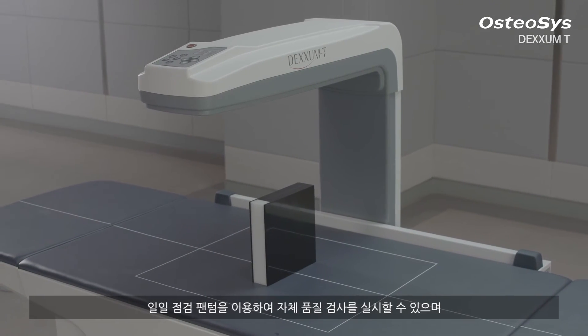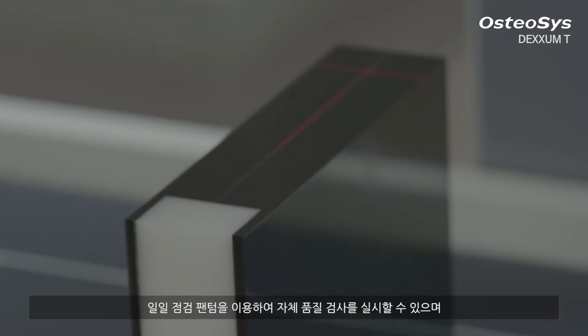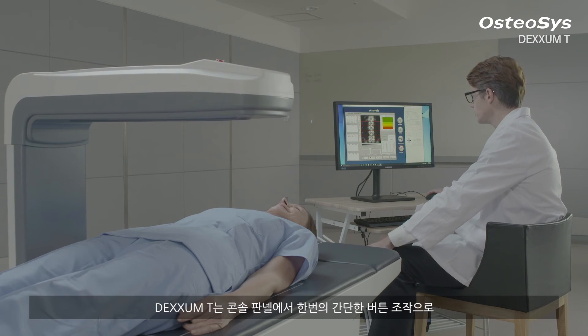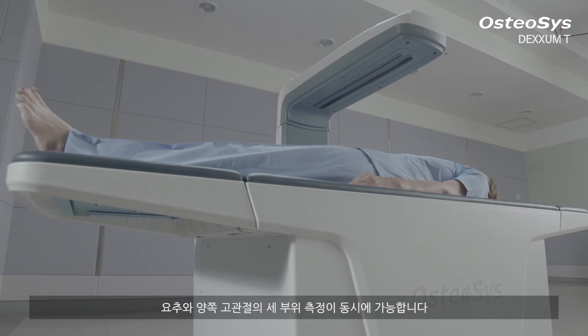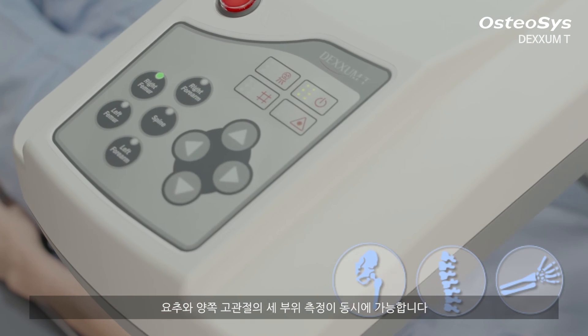To maintain the high quality of system performance, DEXXUM T has an automatic quality test function using a daily examining phantom. With only one simple touch on the console panel of DEXXUM T, you can measure three major areas — AP spine and dual femurs simultaneously.